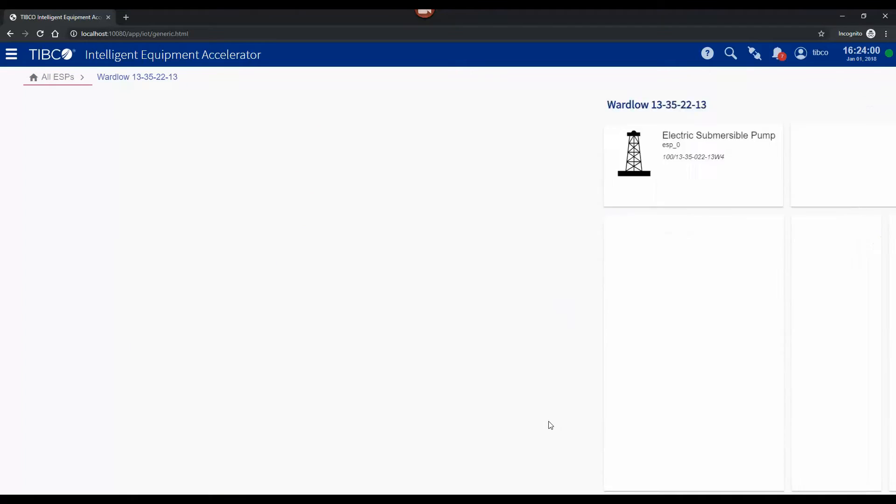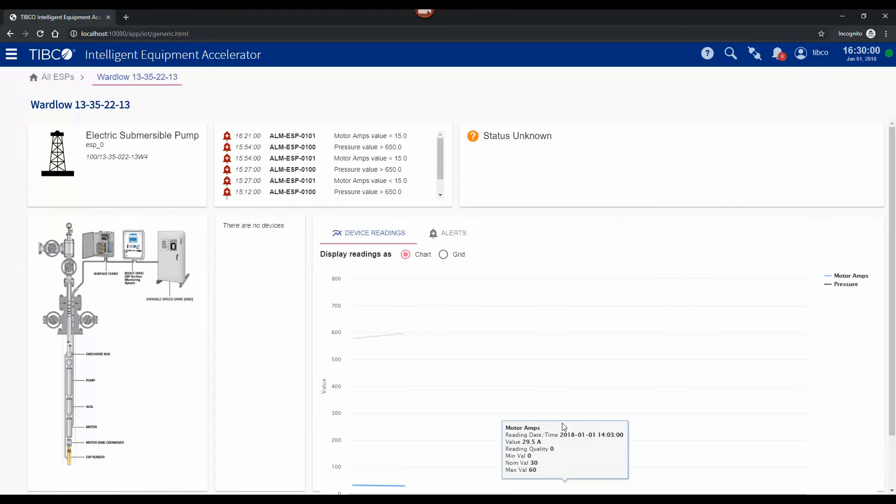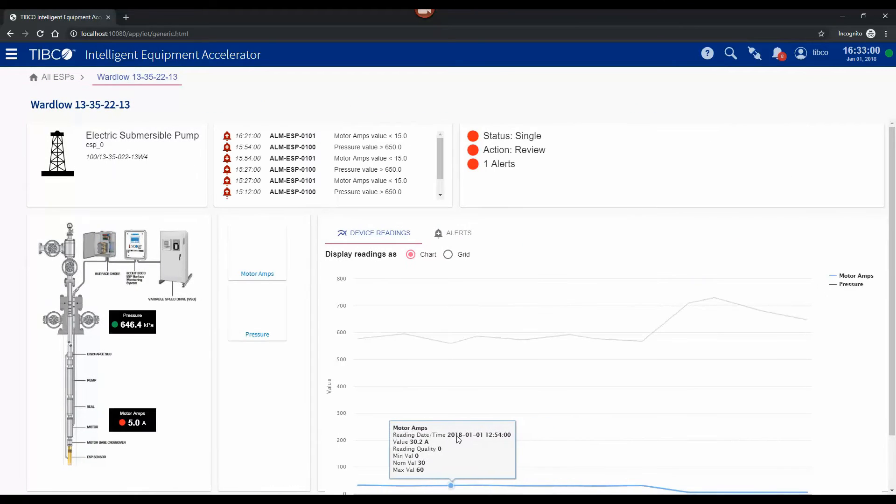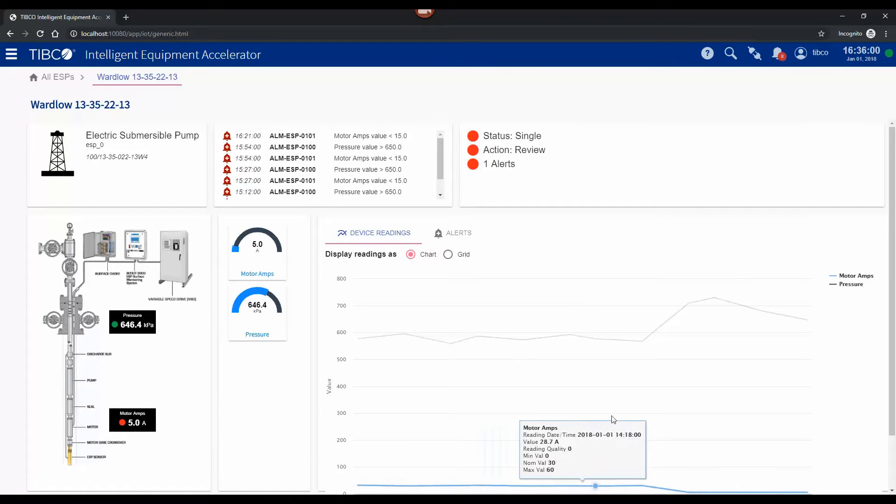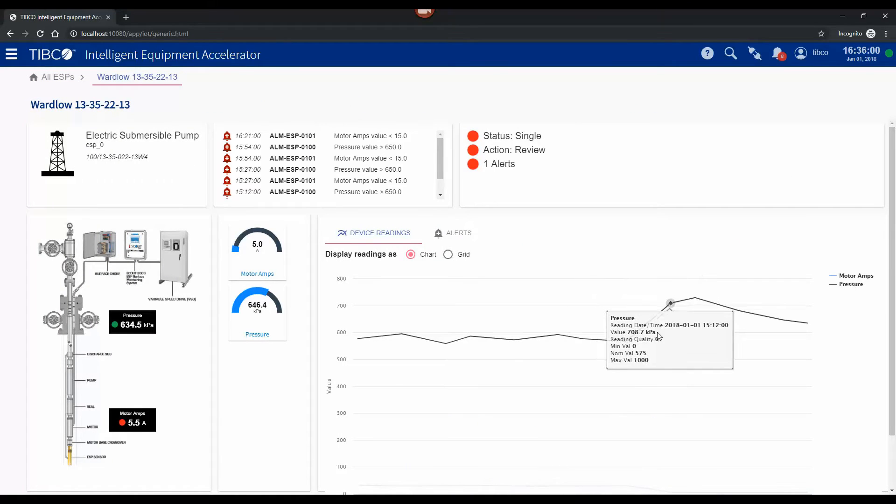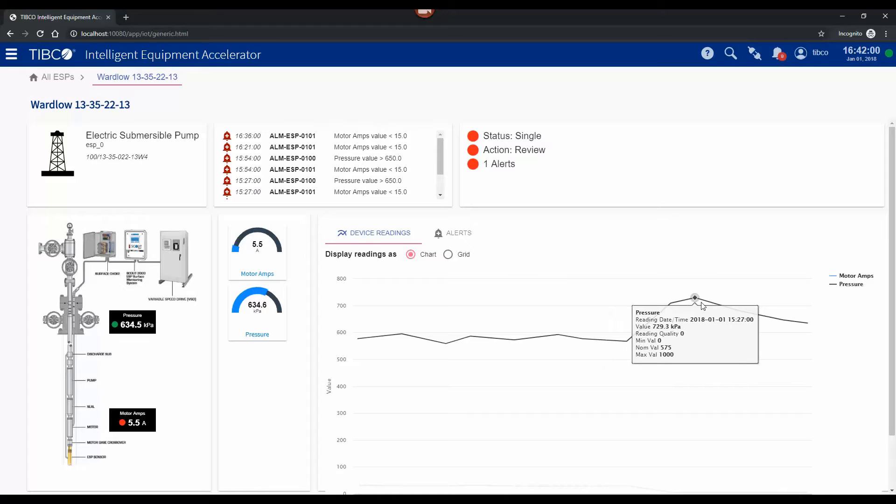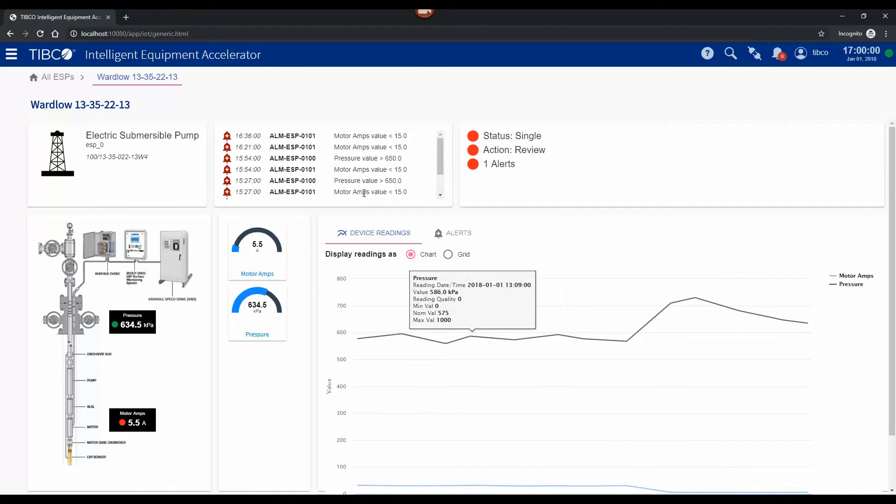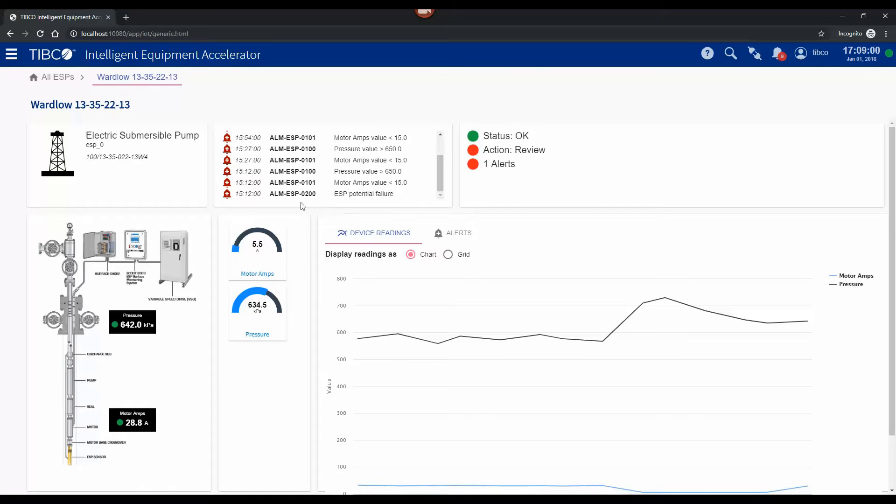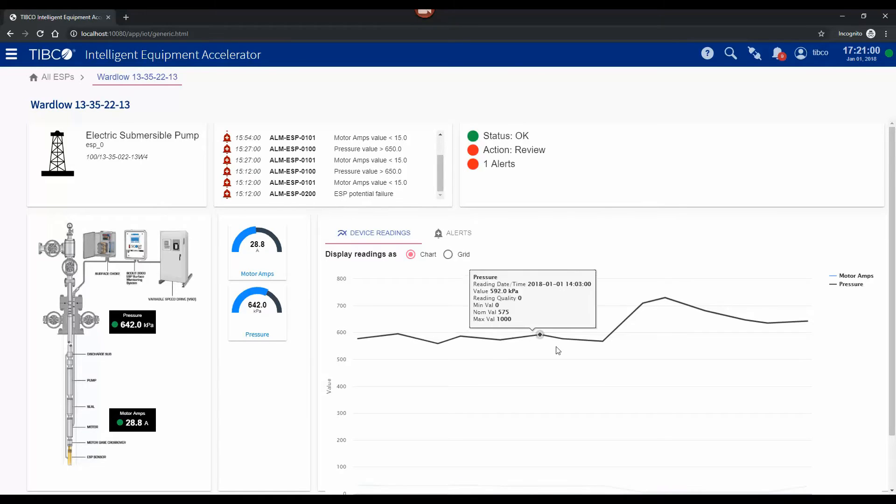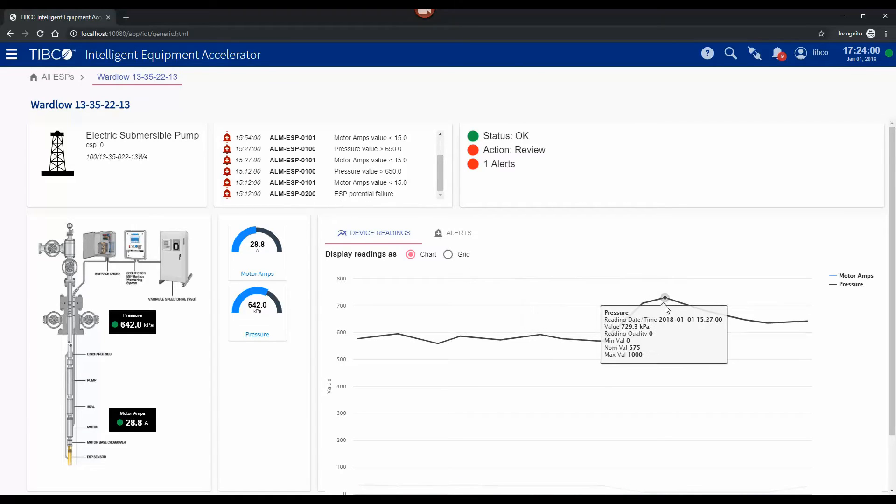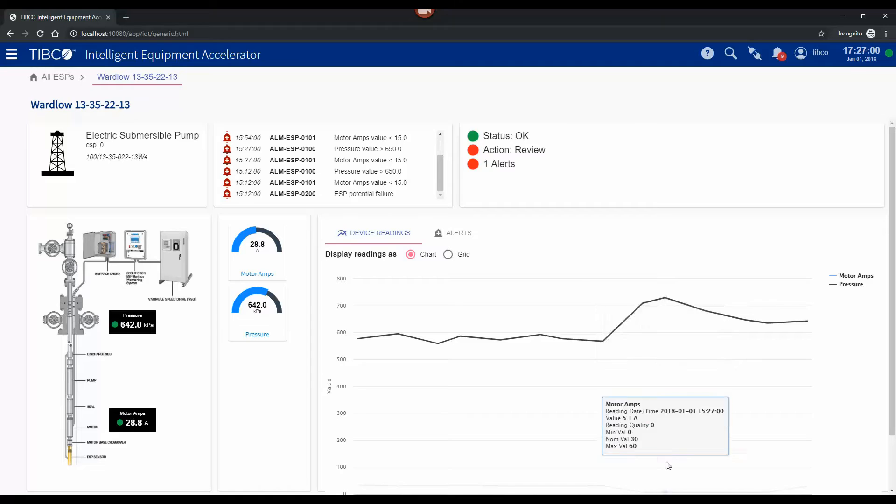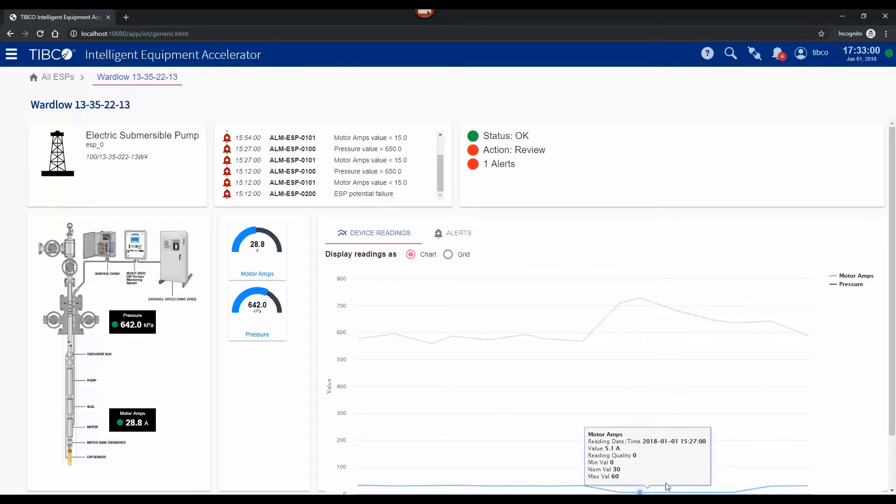If I go and select that well now we can look at the details of that. You can see the pattern where the pressure is rising and then the motor amps has dropped. We have a number of alarms that have been raised here including this one which says ESP potential failure and that's detected the pattern of this rise and this drop occurring at the same period of time.